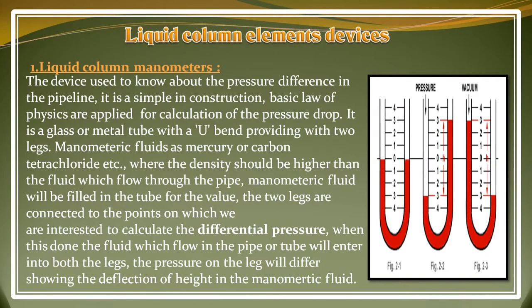The liquid column manometer is a device used to measure pressure difference in a pipeline. It is simple in construction and basic laws of physics are applied for calculation of the pressure drop. It is a glass or metal tube with a U-bend providing two legs. Manometric fluids such as mercury or carbon tetrachloride are used, where the density should be higher than the fluid flowing through the pipe.